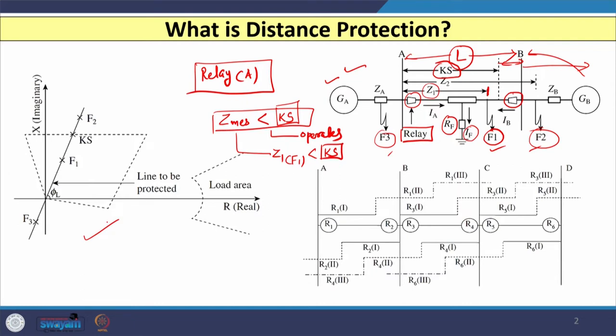Distance relay has different characteristics: impedance characteristic, mho characteristic, quadrilateral characteristic, lenticular characteristic, elliptical characteristic, and so on. The most widely used characteristic is the quadrilateral characteristic. All characteristics of the distance relay are shown on the R-X plane, with R or the real part on the X-axis and X or the imaginary part on the Y-axis.